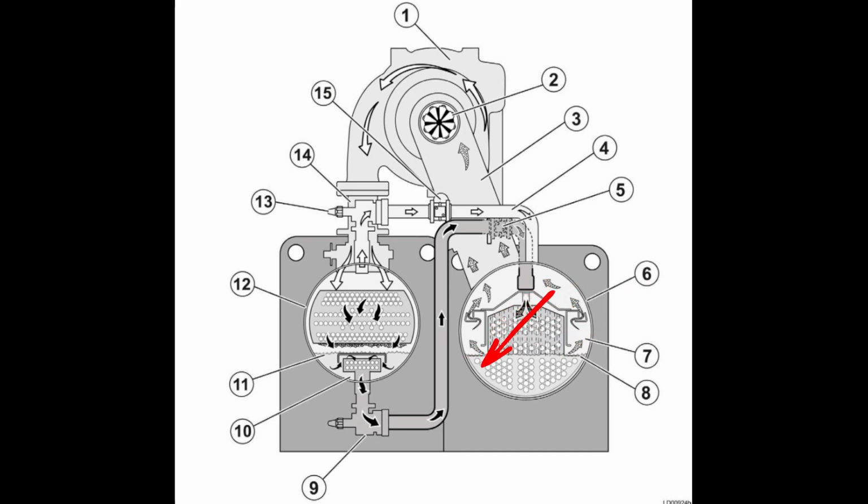And if you have a sight glass, one of the ways to know if you're heavily oil laden is by how much foaming action you have in there. The more oil you have in a system, the more foaming action you will have at that top layer of boiling. And many times it'll have a yellowish or orange tint to that foaming. It won't be just white.